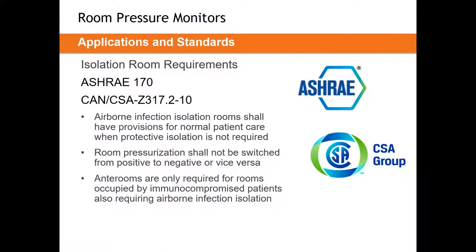Airborne infectious isolation, protective environment, and the combination of the two are all pressurized negative or positively. ASHRAE 170 also states that once a room is designated negative, it can never go neutral or positive — negative rooms must stay negative and positive rooms must stay positive, unless you go through the process of recommissioning these spaces. You cannot switch these rooms from one side to the other.